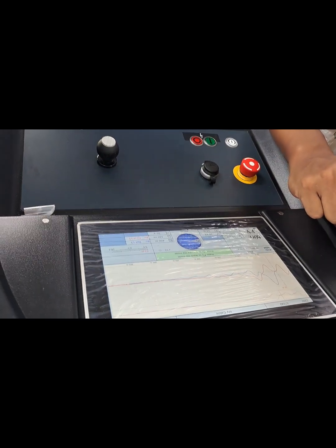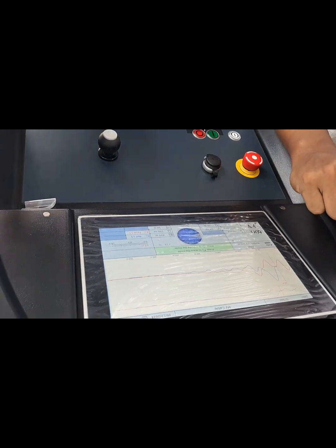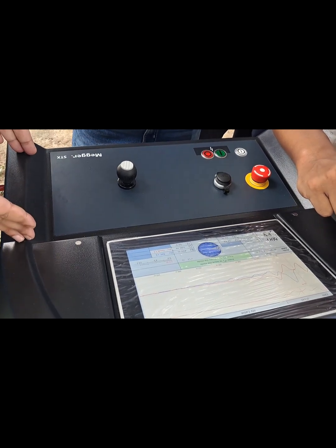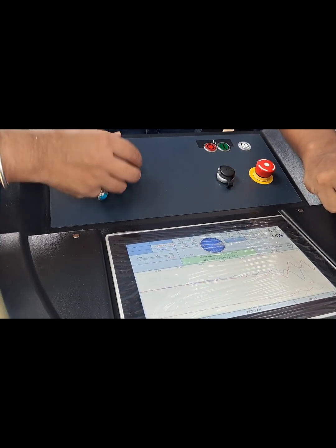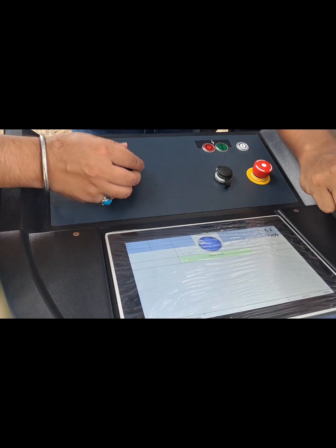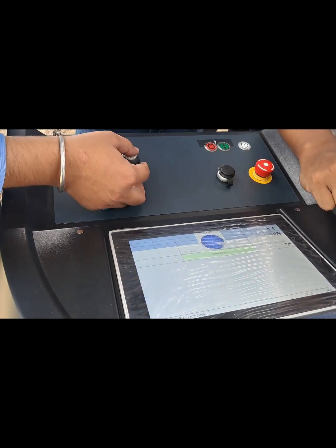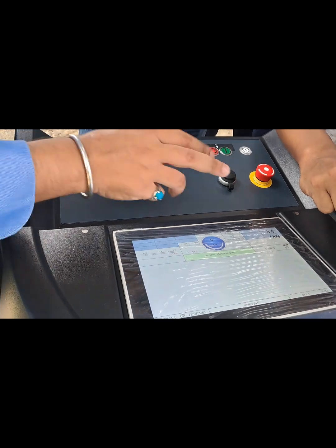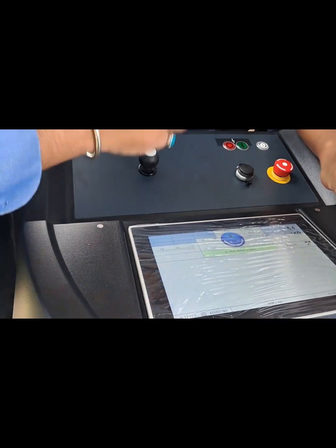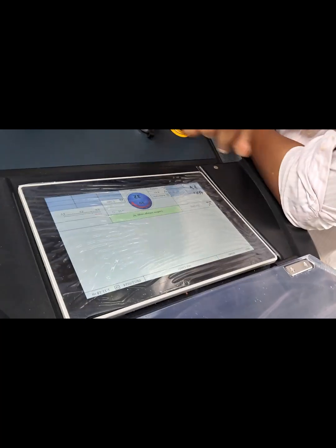Now you understand that, suppose my cable length is 100 meters and 35 is the fault distance. But where exactly is the 35 meters? To get this, we have to go into pinpointing, surging. We have to select the range again. Suppose I am taking 30 kV, how much? Maximum 32 kV is there. Maximum surging is 32 kV.